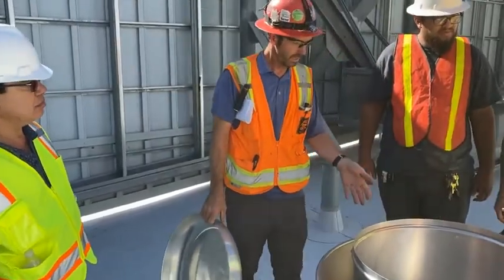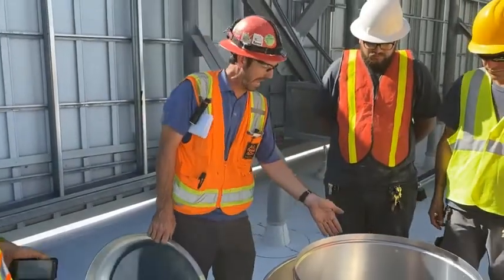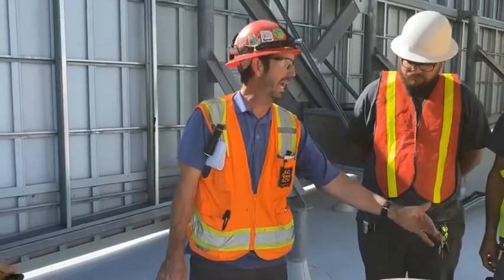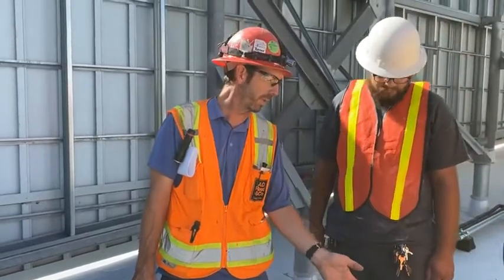All of the grease fans do not have screens on the outlet of the fan, okay? Be very careful. This one is not a grease rated fan, so there is a screen around the blower wheel. All the other mushroom fans do not have screens, so do not reach down inside the fan with it running, okay?